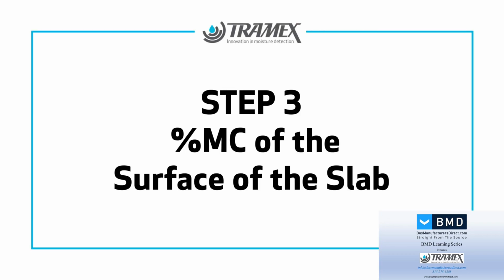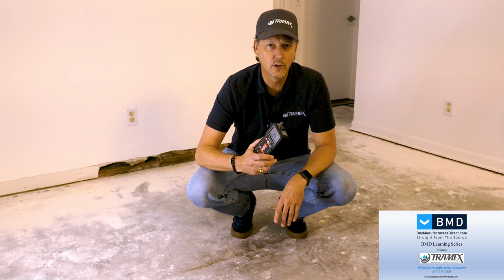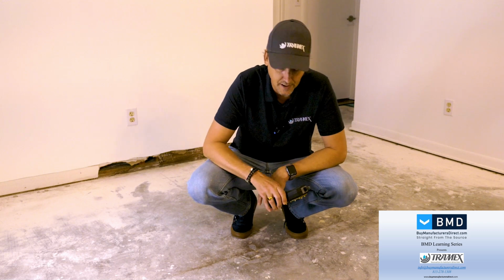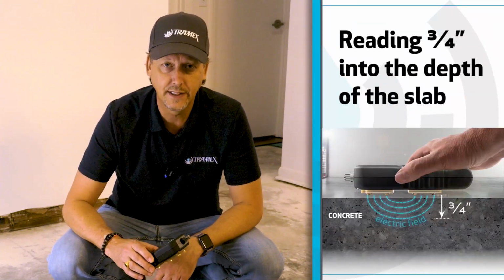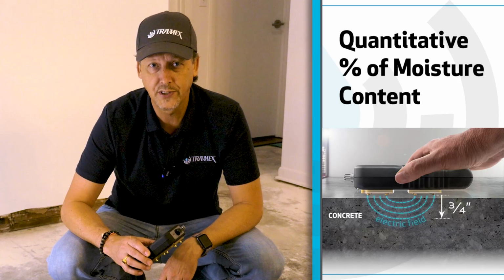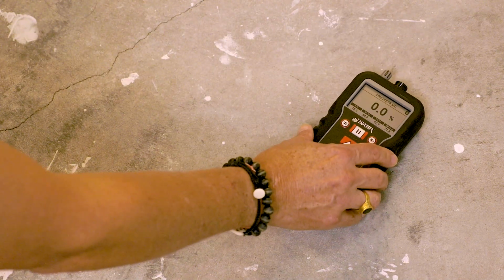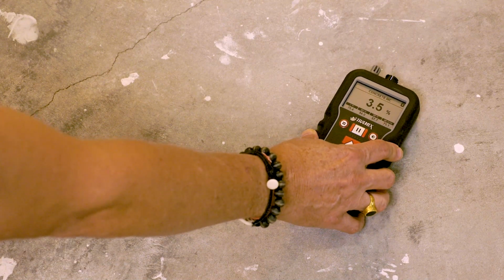Now, the last step to perform in the installation quick check is to take a reading with the concrete moisture encounter on the surface of the slab. The nice thing about the concrete moisture encounters is that they're reading 3/4 into the depth of the slab and giving an actual quantitative percentage of moisture content reading. So when we take the surface reading, we want to make sure that we have a cleaned area. So we've abraded this a little bit and gotten any residue off the surface of the slab, avoiding any paint or drywall mud. We're just going to press the meter on the surface and get a reading.